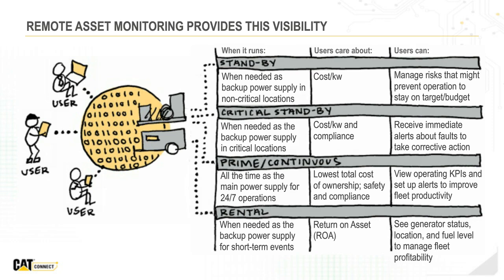We also see, for both standby and critical standby, requests to remote start and stop the genset. In commercial applications, if there's an impending storm, for example, or any issue that's going to disrupt power, you can remote start and stop the genset ahead of time and check for any faults or alarms that would prevent it from operating when you really need it.